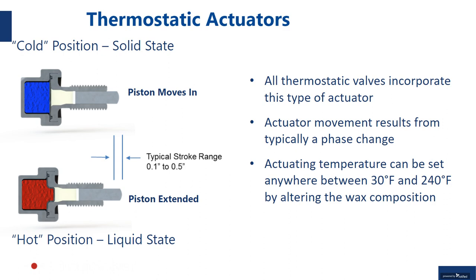So the way you get the largest stroke out of this type of actuator is going from a solid to a liquid. When you go from a solid to a liquid, you're getting the maximum change in volume. As that volume increases with temperature, the wax starts pushing on a diaphragm, and that diaphragm extends a piston. So as temperature increases, the wax goes from a solid to a liquid, the volume expands, and the piston extends. As the temperature cools down, the wax goes from a liquid back to a solid, the volume compresses, and the piston retracts.